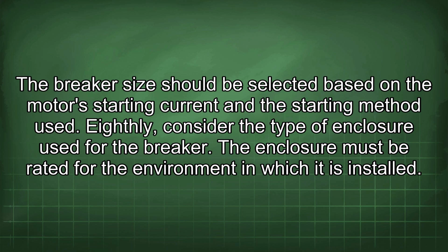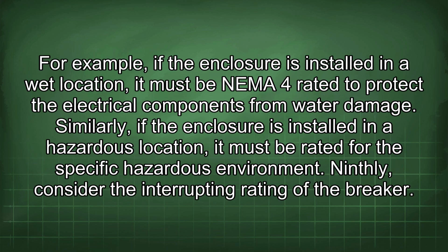Eighthly, consider the type of enclosure used for the breaker. The enclosure must be rated for the environment in which it is installed. For example, if the enclosure is installed in a wet location, it must be NEMA 4 rated to protect the electrical components from water damage. Similarly, if the enclosure is installed in a hazardous location, it must be rated for the specific hazardous environment.